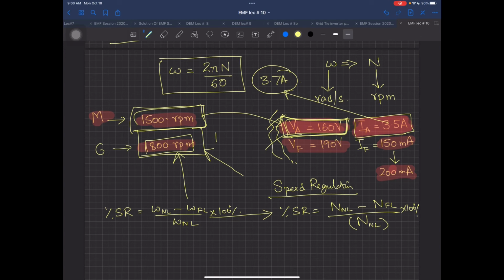All those orange color machines inside your lab with adequate size, they are like 400 watts of power. They are like student made, not industrial grade, and deliberately so, since you will be trying to find out the efficiency of those machines, so their power is small and their losses are a little larger than the normal one, so that you can have an adequate number of values and you can measure it. So the power rating of those machines is limited to like 400 watts. The motor rated speed is 1500 RPM, the generator rated speed is 1800 RPM.